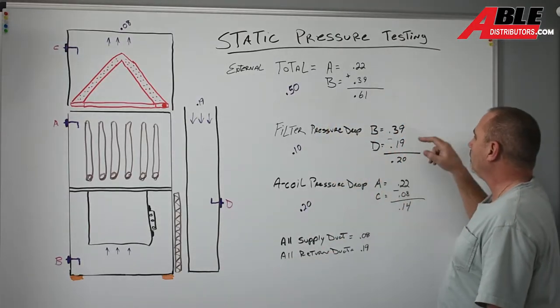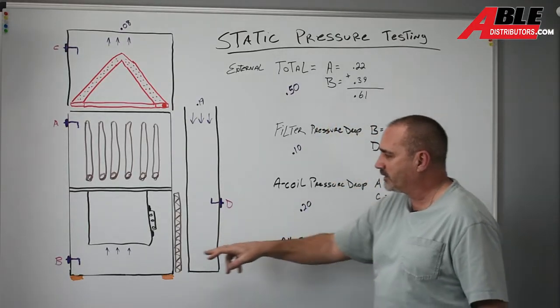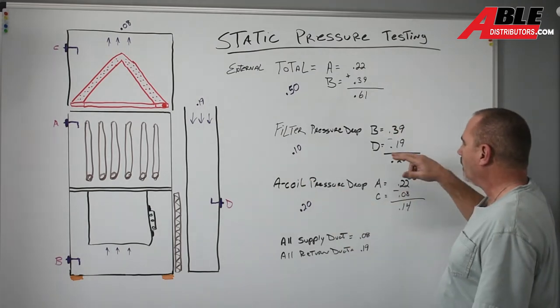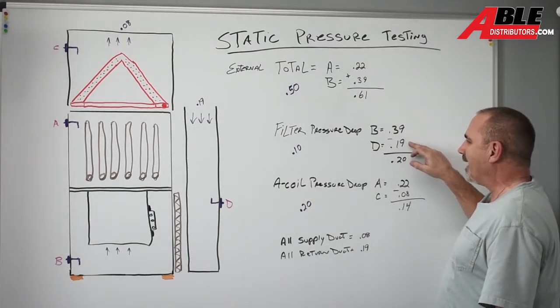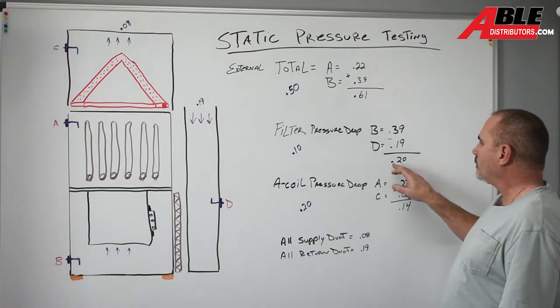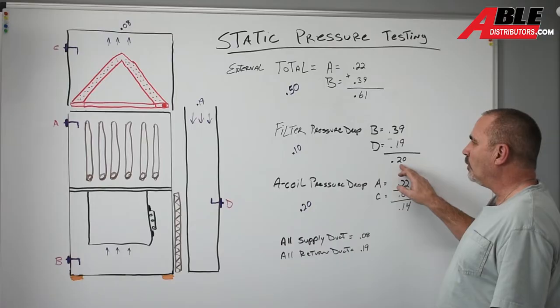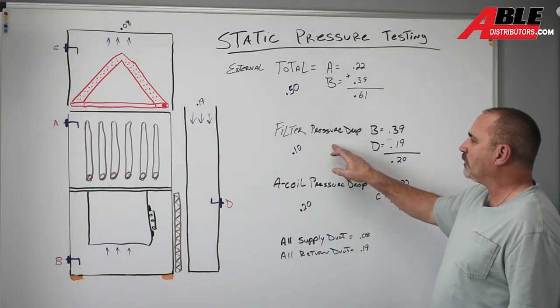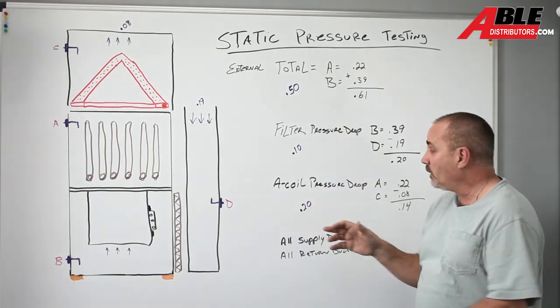So in this situation B again was 39, that's not going to change from what it was before. D I had 19 here. So that means we're losing 0.2 across the filter. Most filters are 0.1, so we know we got an issue there.